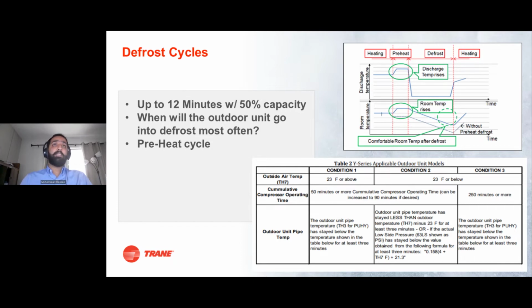We also have a preheat cycle built into all of our indoor units. What this means is that before the system goes into defrost, it will raise the leaving air temperature on the indoor unit for 3 minutes in order to make sure that during the period of reduced heating, the space temperature and the occupant comfort is not lost too much. It is important to remember that we as a manufacturer get a lot of defrost calls when it's a lot closer to dew point rather than when it's very cold outside, and that's just because there's more moisture in the air at that temperature, and it just freezes more on the condensing coil.